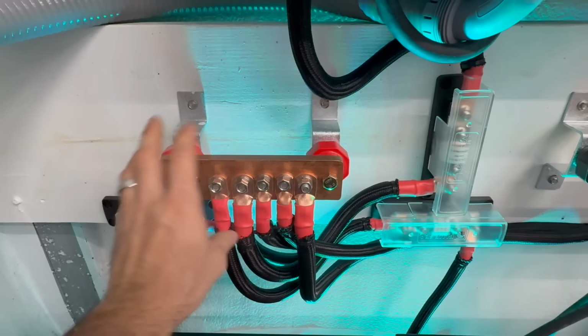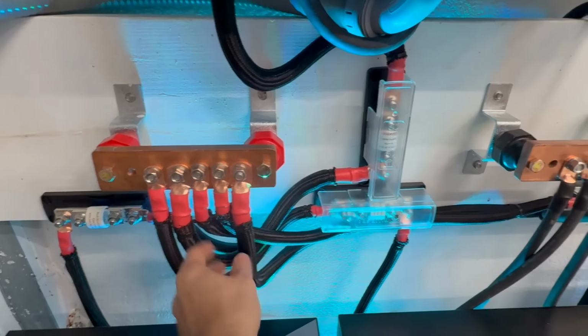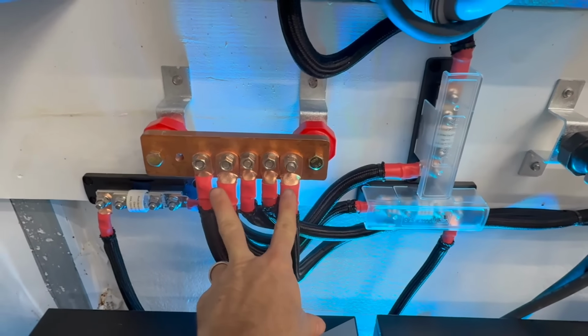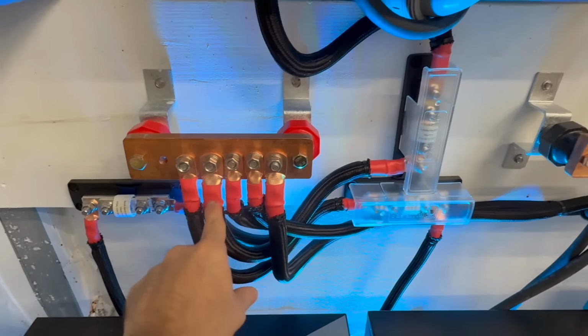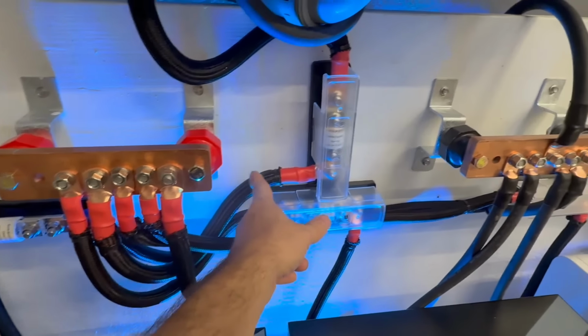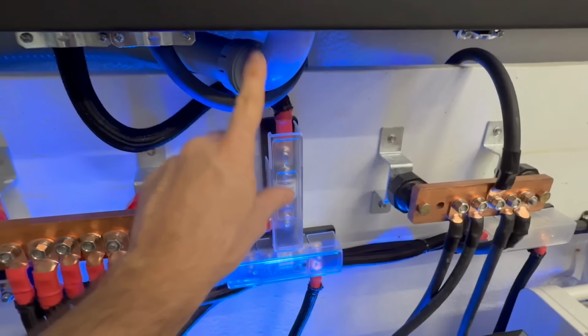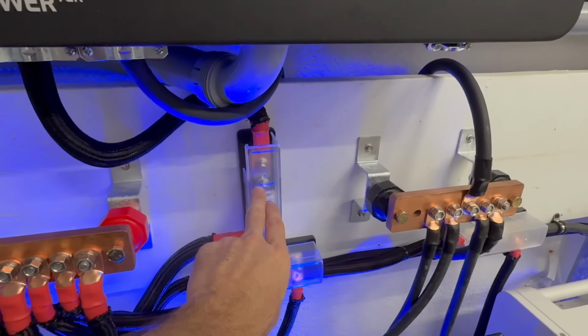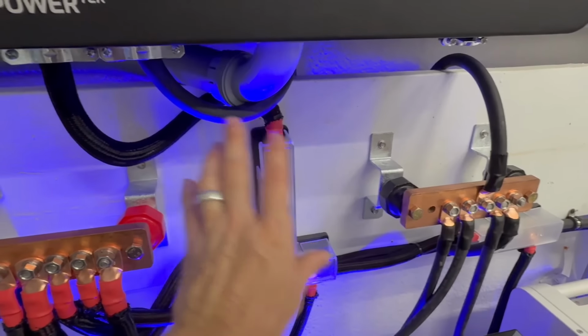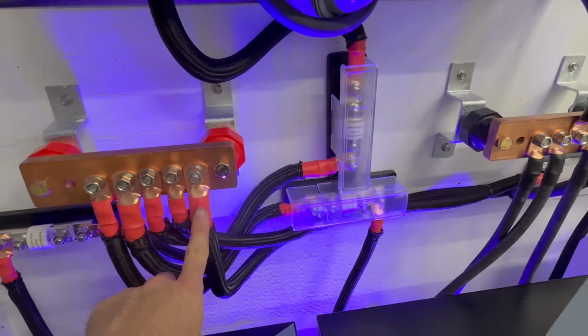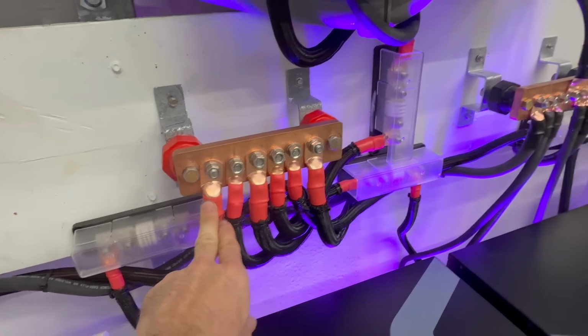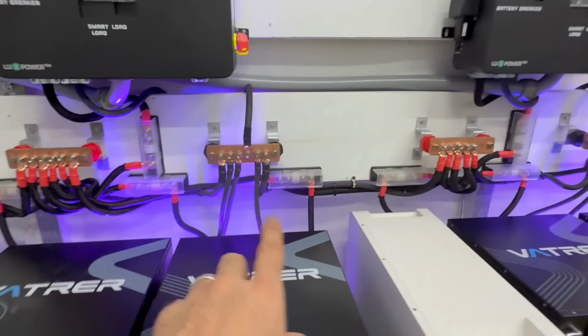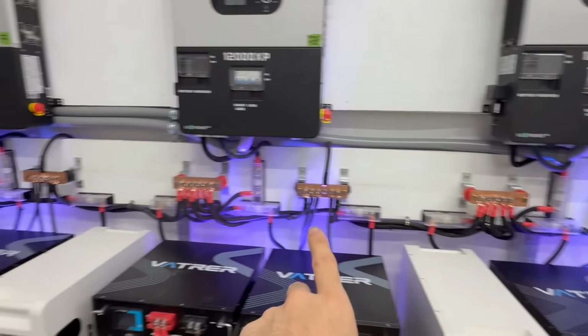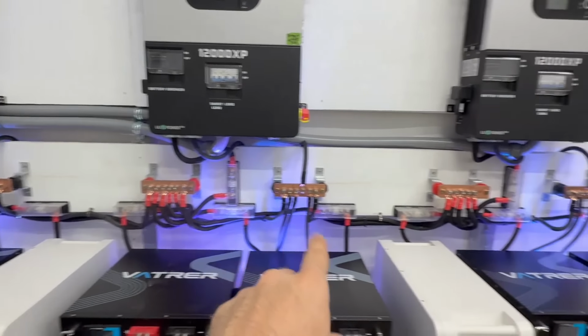So it goes up to the bus bars, and you can see I have 2 4-aught cables. One 4-aught cable comes out, goes into this T-class fuse, and then into the inverter. That way, if I have an issue with the inverter, this fuse will blow and save me. Then I have another 4-aught cable which goes all the way across and connects to this bus bar. So stepping back, each of the positive bus bars are connected together with 4-aught cable, and each of the negative bus bars are connected with 4-aught cable.